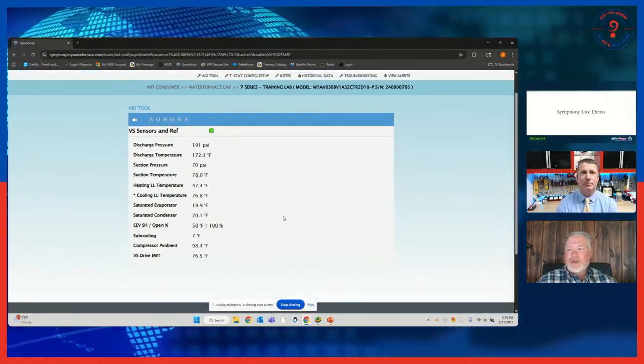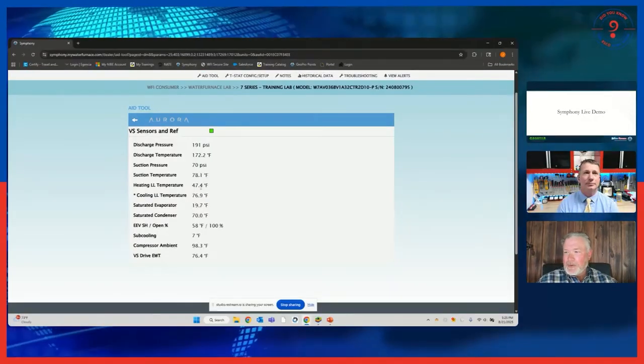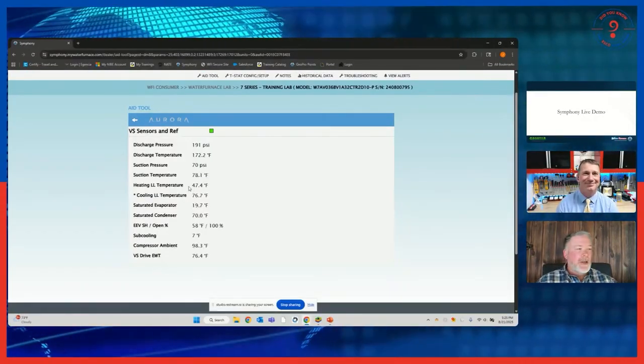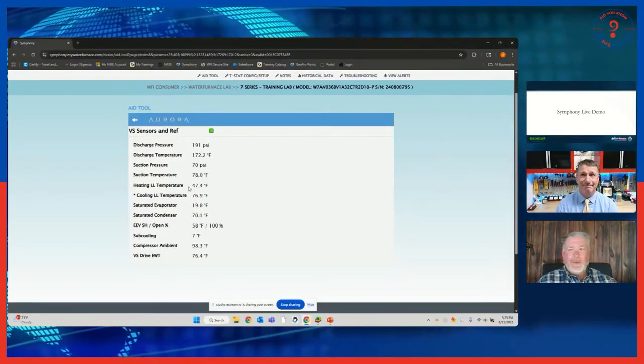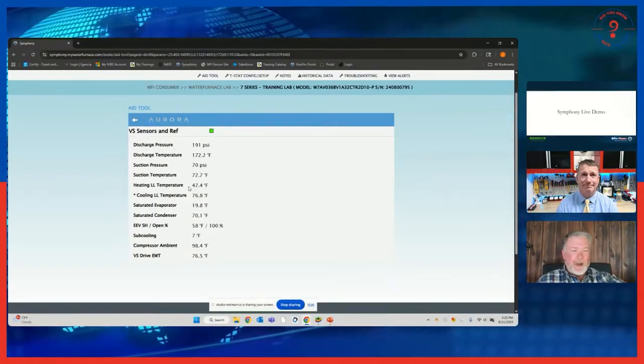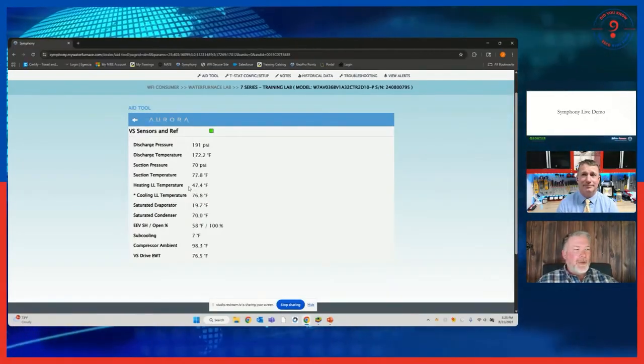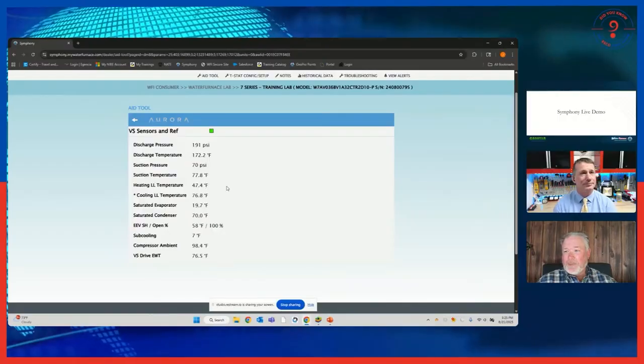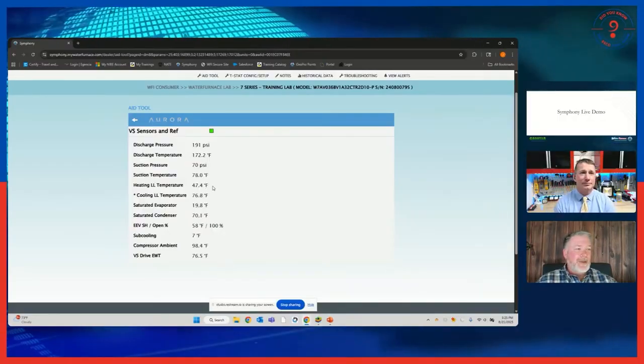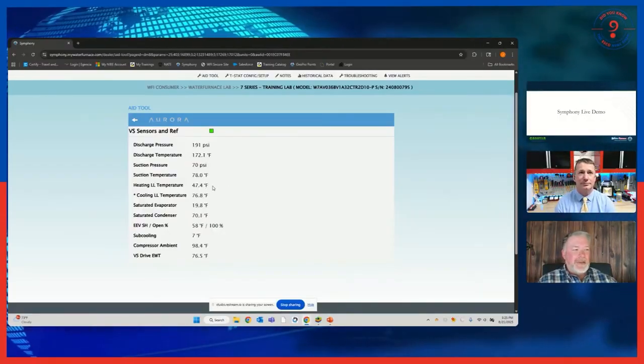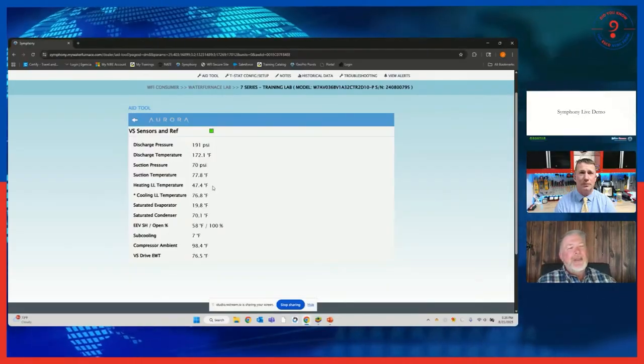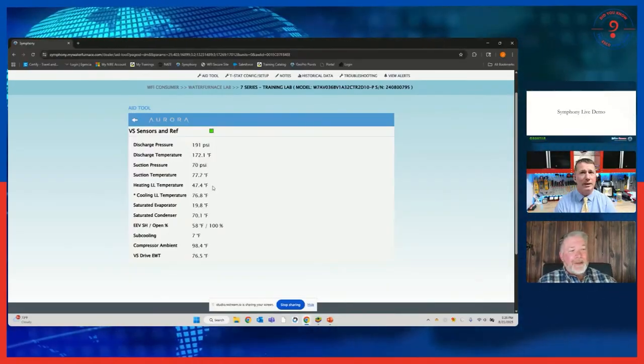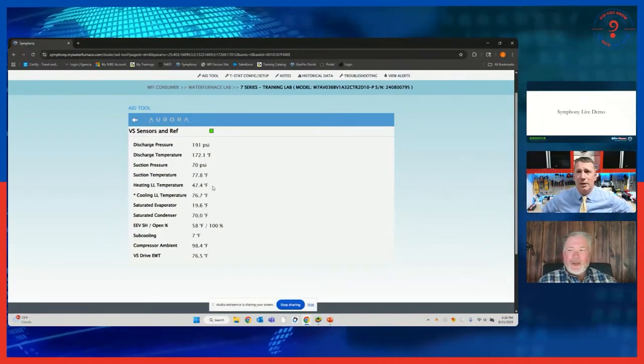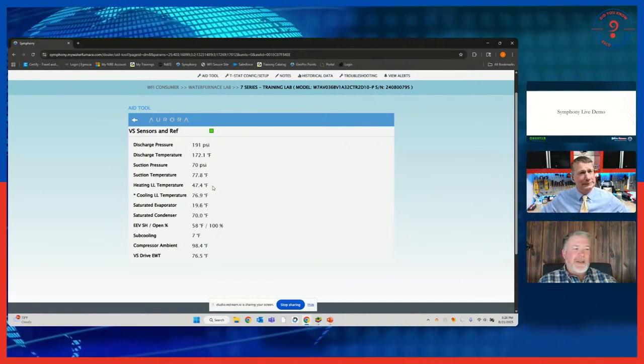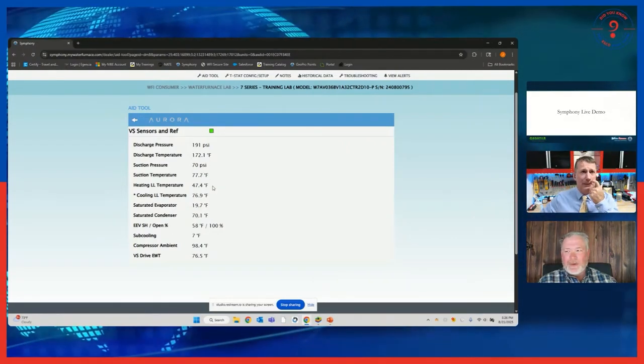Much easier. Here's my heating liquid line temperature. Right now it's 47.4. That's what my board's reading. So all I've got to do is get my temperature probe out, clamp it on, see what it reads, see what my board is reading, and that's it. I don't need to get that ohms chart out. Now, if it were off, I would probably want to verify it. But the first glance readings, absolutely. Just amazing what that'll do.